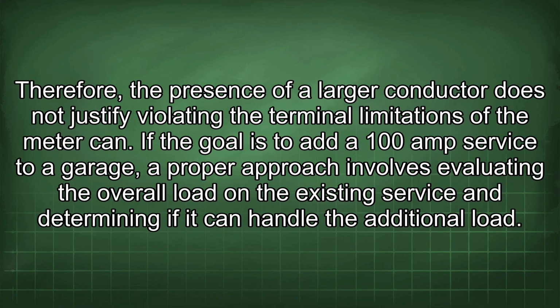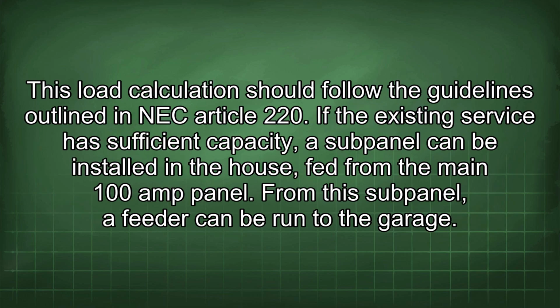Therefore, the presence of a larger conductor does not justify violating the terminal limitations of the meter can. If the goal is to add a 100 amp service to a garage, a proper approach involves evaluating the overall load on the existing service and determining if it can handle the additional load. This load calculation should follow the guidelines outlined in NEC Article 220.